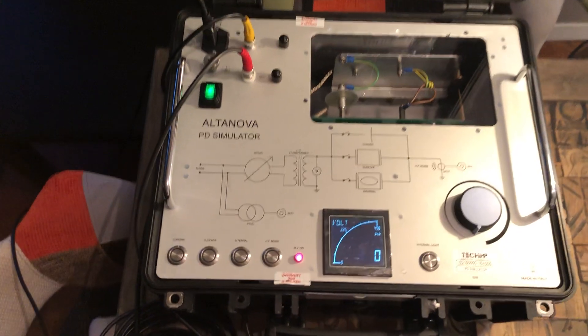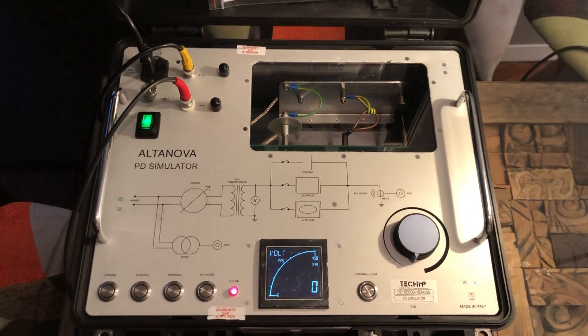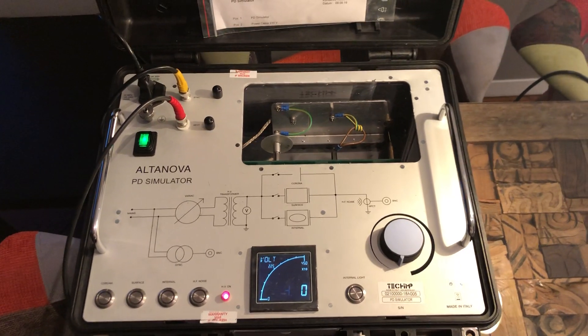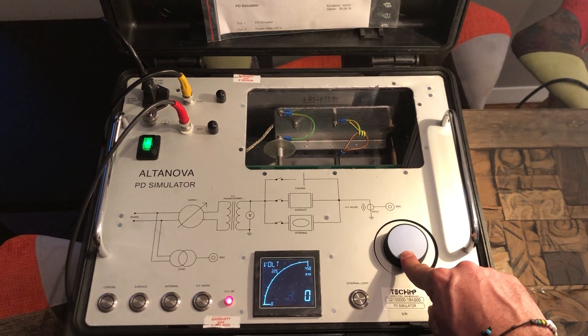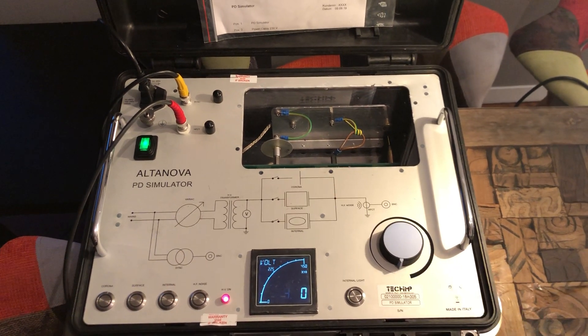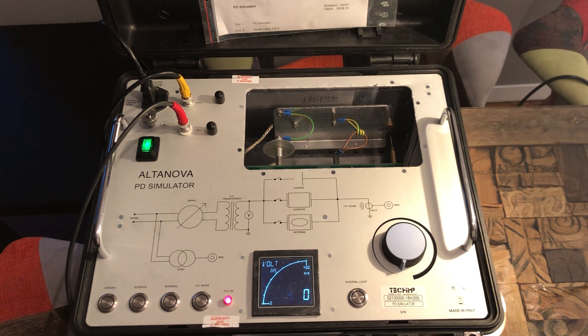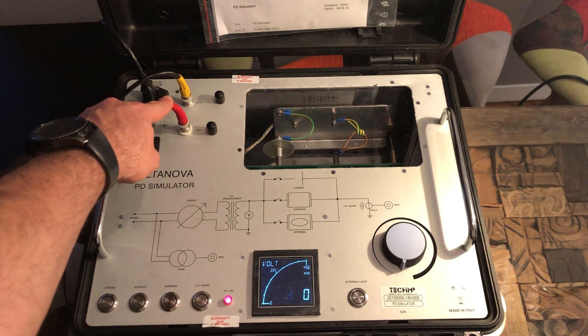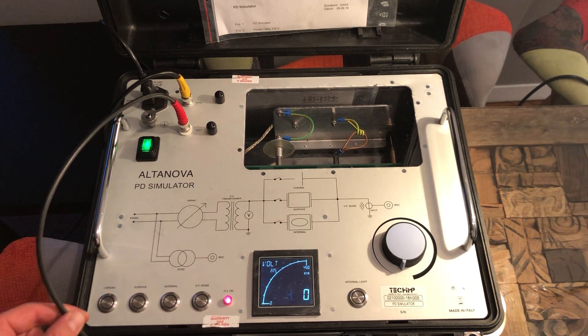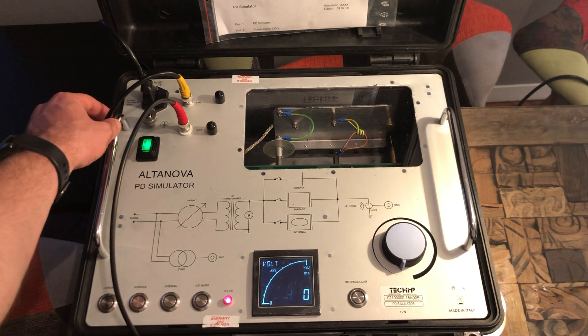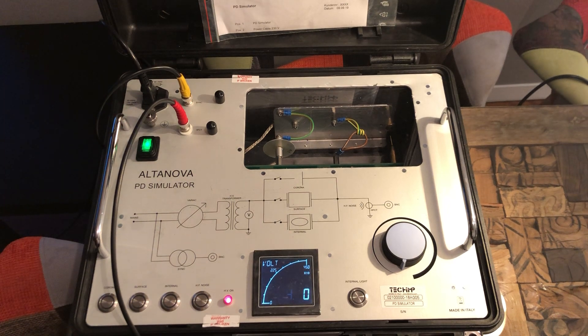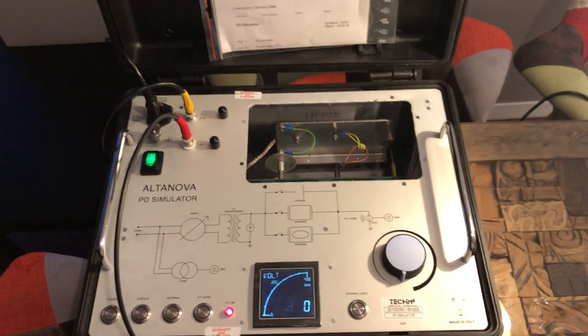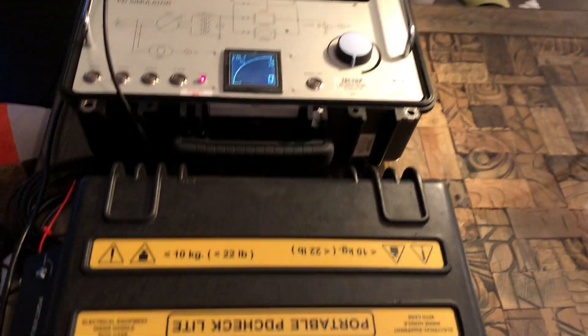So we can take a closer look. Because the PD is dependent only on voltage, we will be able to change the voltage by rotating this knob. What I did already is I have connected the output of this simulator, which is the high frequency PD signal, and I have also connected the sync signal, which is the 60 Hertz, 50 Hertz signal. I've connected that to my acquisition unit.